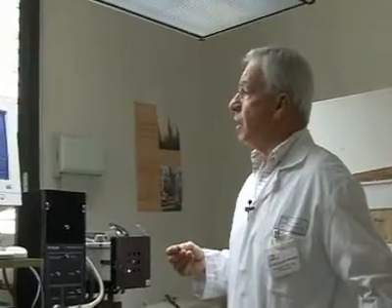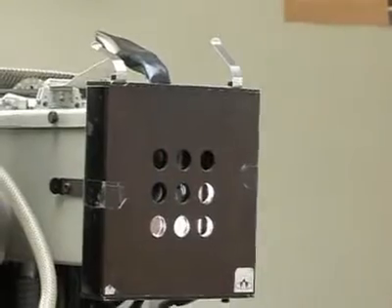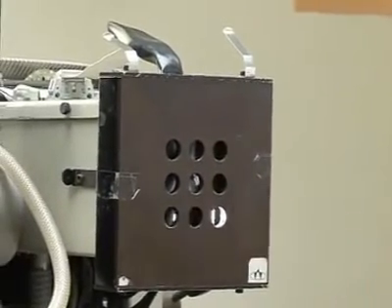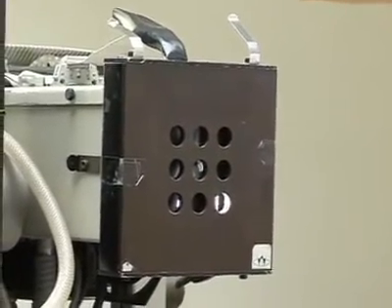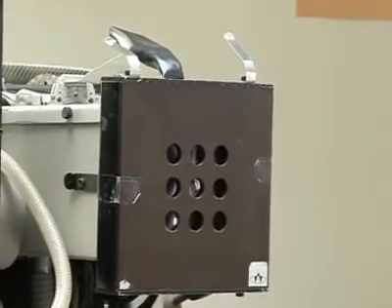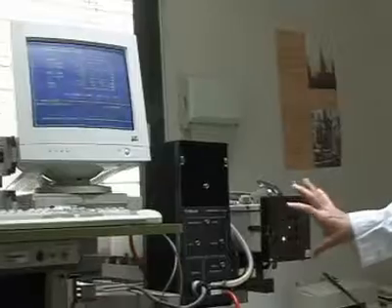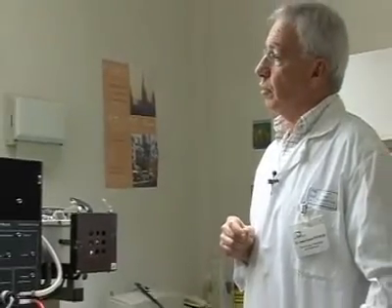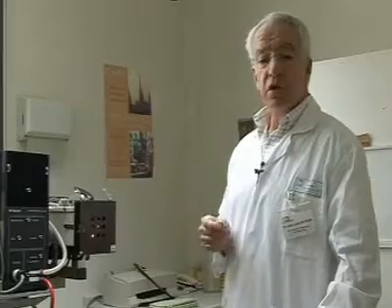We programmed the doses, which you can see here on the screen, which correspond to the ones which will be administered behind this cover. The doses will be administered by the successive opening of these covers, in such a way that when the patient puts his back against the plate, he can receive the radiation very gradually — what we call the determination of the MED, the minimal erythematous dose. Obviously, we can also use it in other situations.